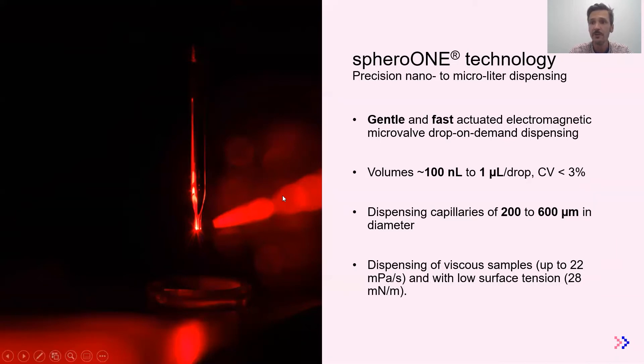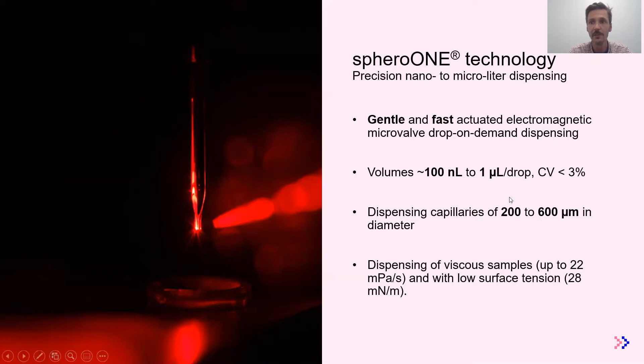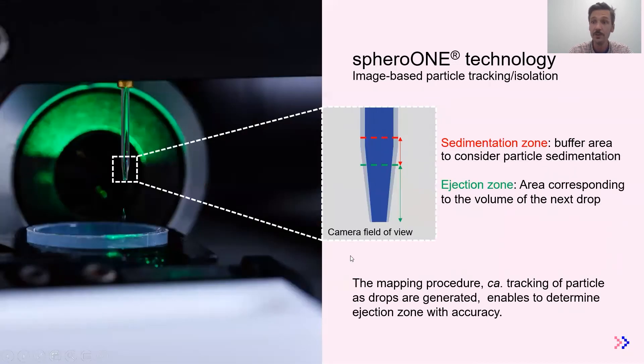Because we want to dispense large cellular aggregates, the capillary we use has an enlarged aperture compared to the standard, with diameters ranging from 200 to 600 micrometers. Just like the standard system, our capillary is placed in front of a camera, which is asked to take a picture before every single drop we generate.